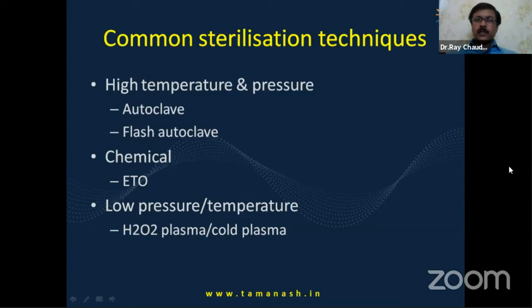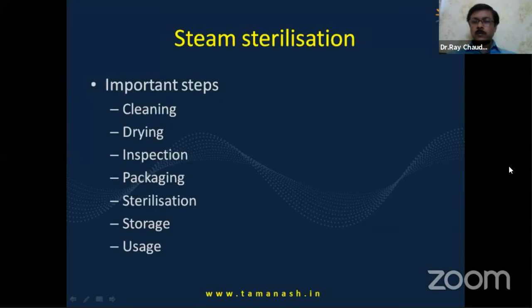The most common sterilization techniques are high temperature and pressure, that is, autoclave and flash autoclave; chemical sterilizers, which work at moderate temperatures and pressures, which is ETO; and low temperature sterilizers, which use H2O2 and or cold plasma. We will be covering autoclave and ETO in this talk because plasma is not widely used in our country. These are the important steps of sterilization, and each step is important, particularly drying and inspection of the instrument. It is not enough to have sterile instruments; you also need working, non-damaged instruments.